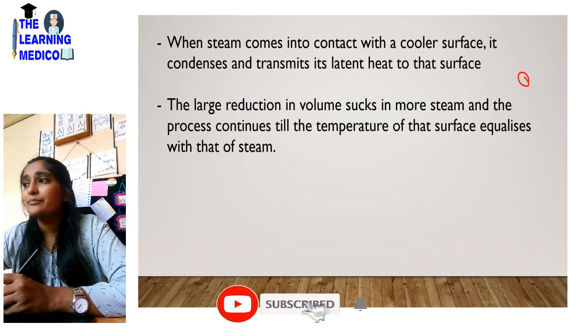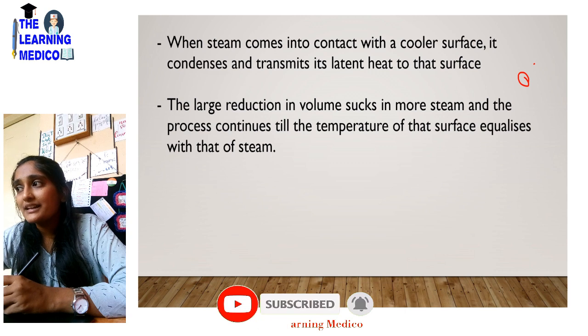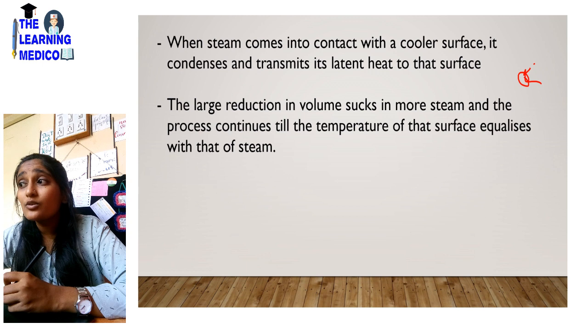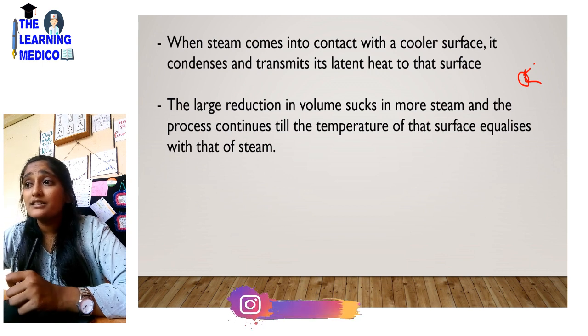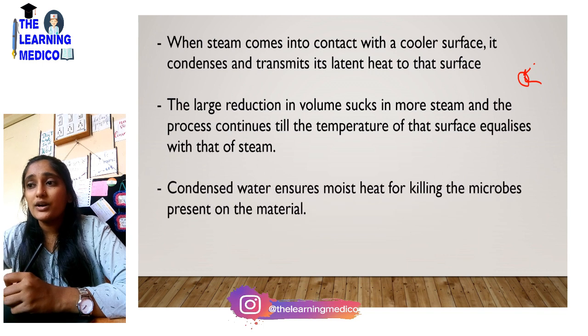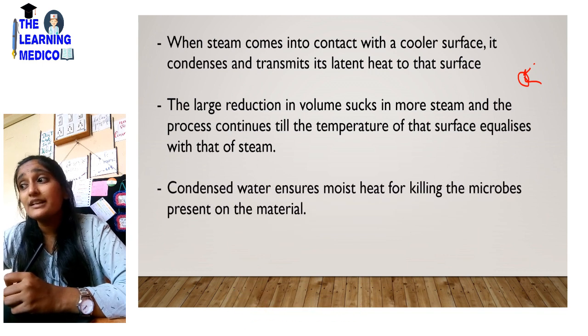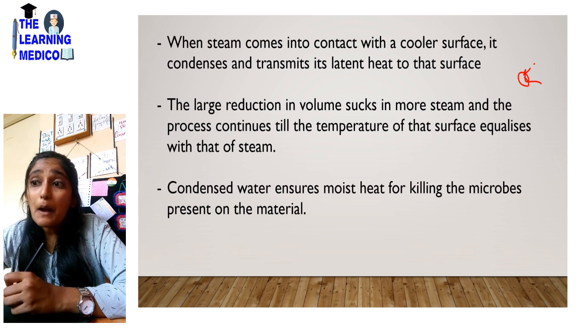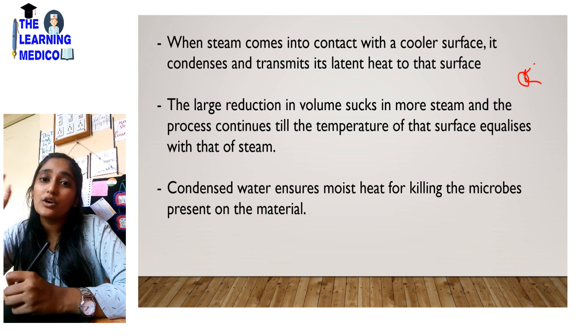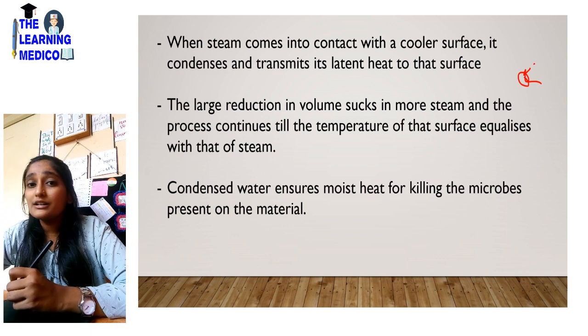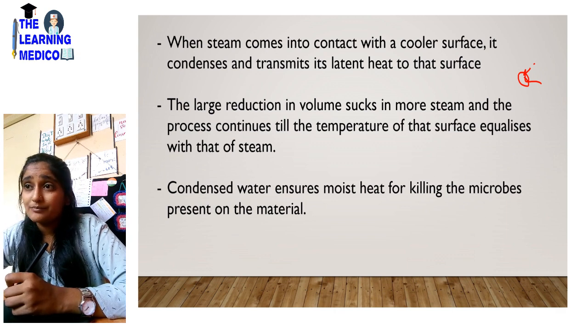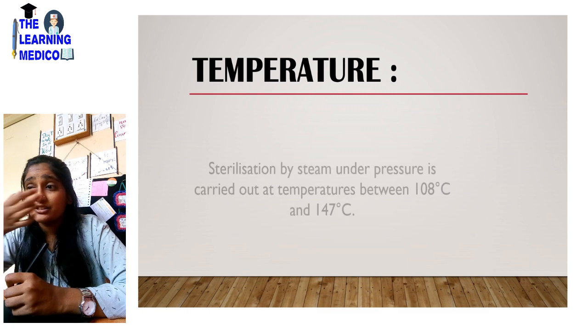The temperature will increase and the steam will be condensed until the temperature of the surface and the steam are equal. Condensed water ensures moist heat for killing the microbes present in the material. When the water is condensed, it releases latent heat — a moist heat that ensures bacteria will be killed.